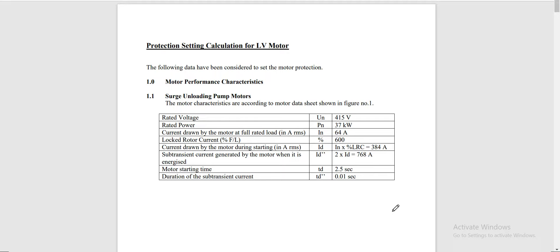Welcome back. Our subject for discussion is protection setting calculation for LV motor. These are the basic data for our motor — it is named as surge unloading pump motor. The rated voltage is 415 volts and the rated power is 37 kilowatt. The full load current of the motor is 64 amperes and the lock rotor current or starting current is rated at 600%, giving a starting current of 384 amperes — simply multiply the full load current by 600%.